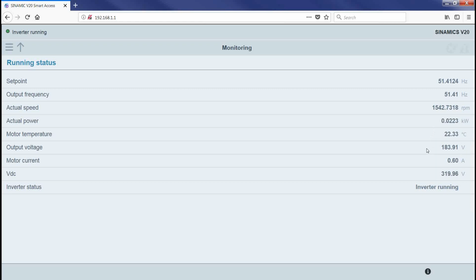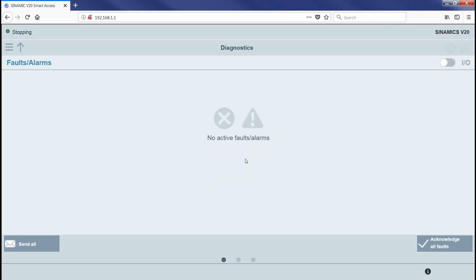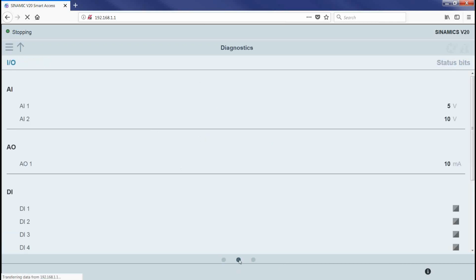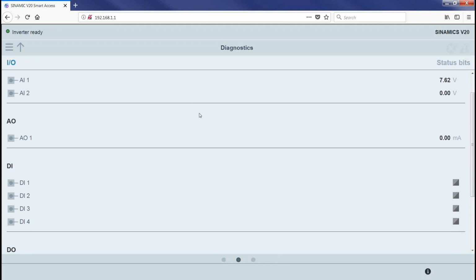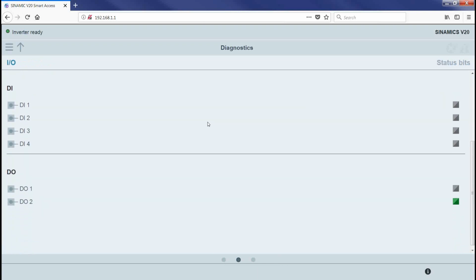All right, so we'll stop that drive. Go up again. Here's your diagnostic view. Currently, no faults or alarms. Again, we got the 3 dots at the bottom, so I'm going to go to the middle one. So this shows our analog. Again, speed pot is tied to AI1, so I can drop the voltage with it or increase the voltage. Analog out isn't configured, so it's not outputting anything at the moment. Digital input 1, again, I can turn it on. We'll see DI1 turn on. So very handy troubleshooting from that.